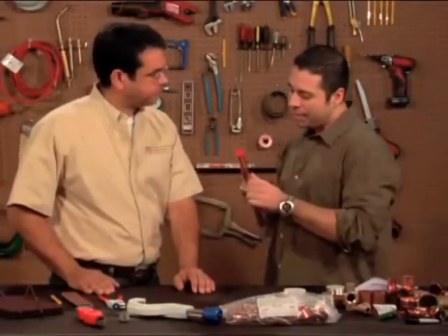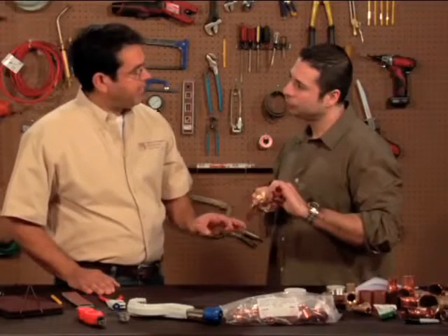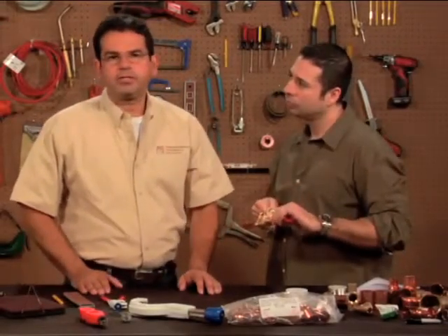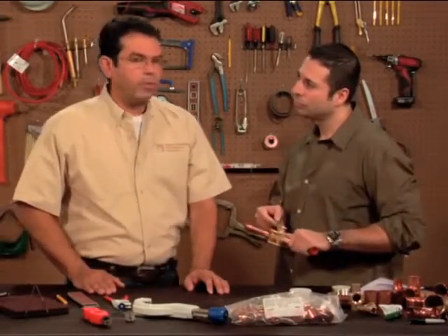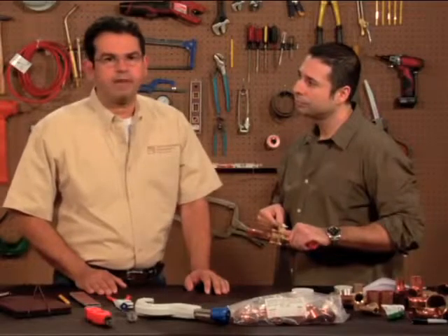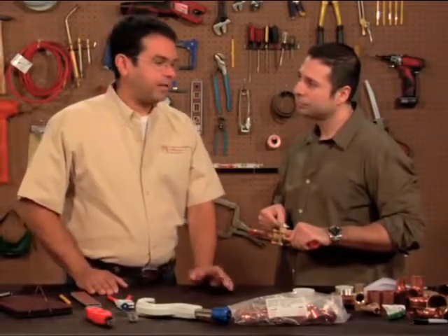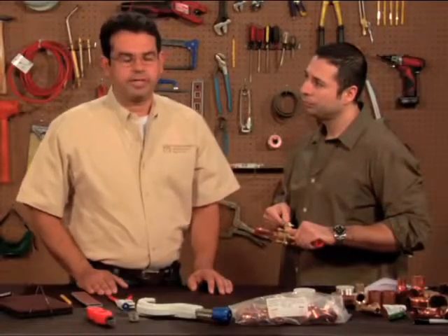Harold, what should be done after the brazed joints are completed? Well, according to NFPA 99, seal the opening to prevent any oxidation and maintain a nitrogen atmosphere until the last brazed joint is complete. At this point, clean each brazed joint with water or a wire brush to remove any oxides on the outside of the tube. Finally, installers and third-party verifiers should complete certification tests.